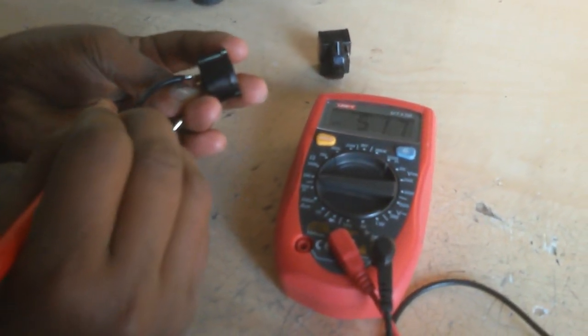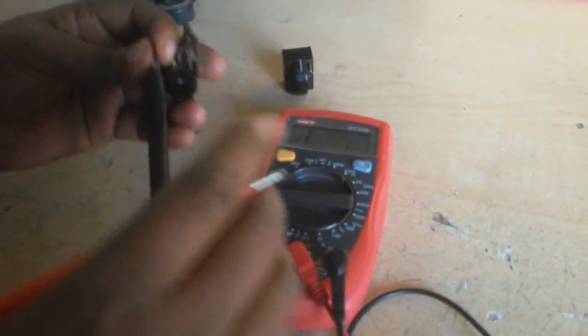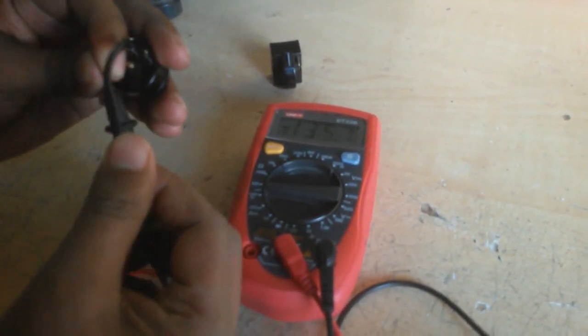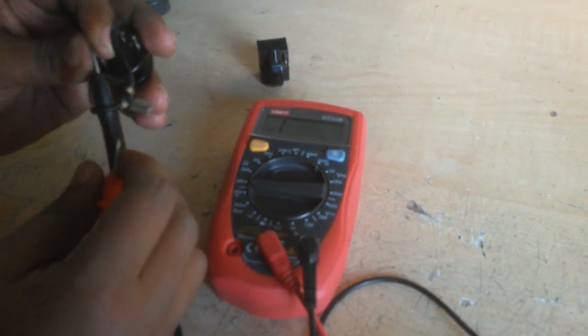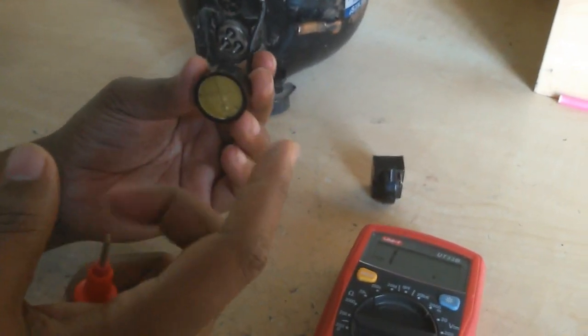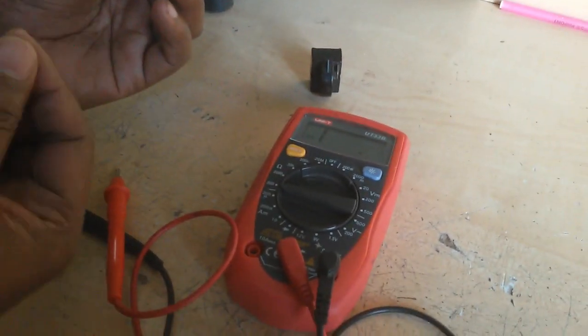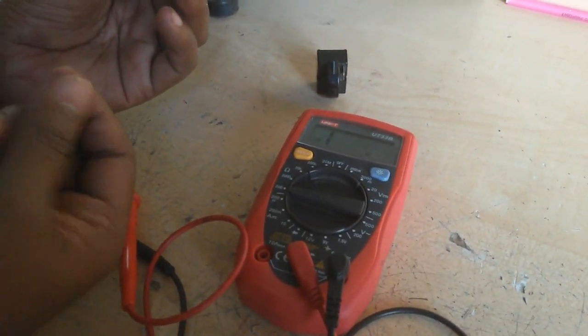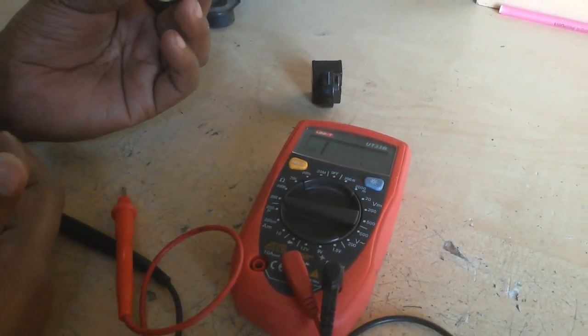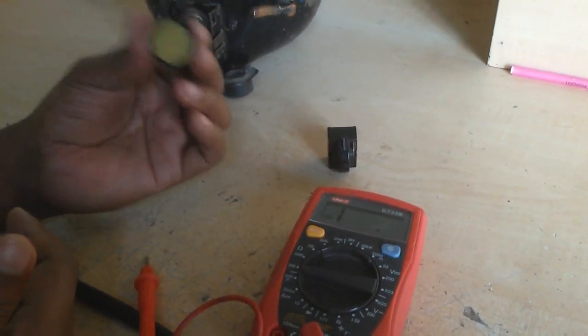It is connected to the terminal meter. Connect the meter — it will show a result. So this is good. It is tested when it is hot or over current — then it disconnects, and again it starts quickly. So this overload protector is in good condition.